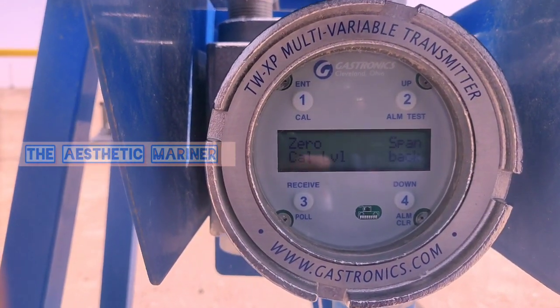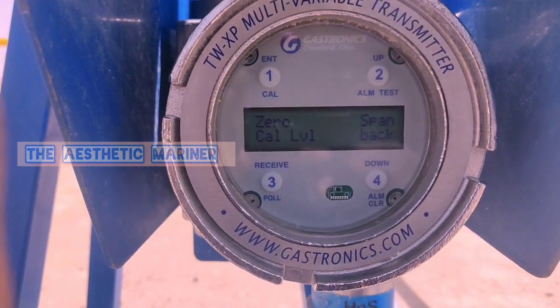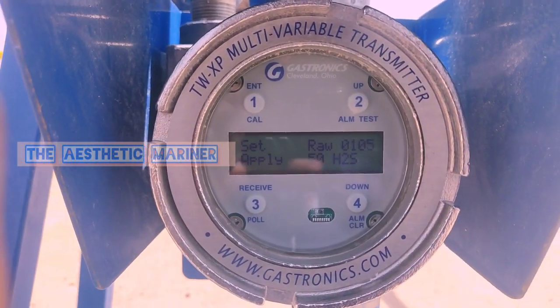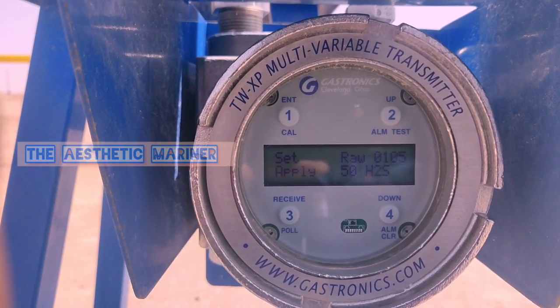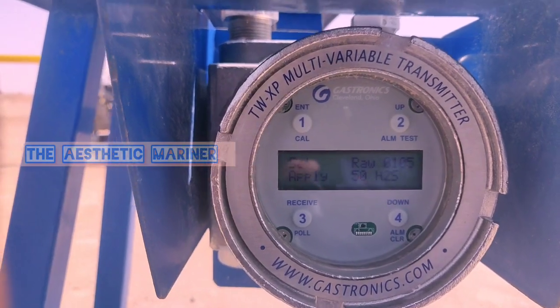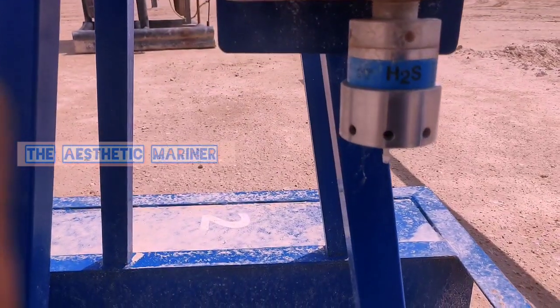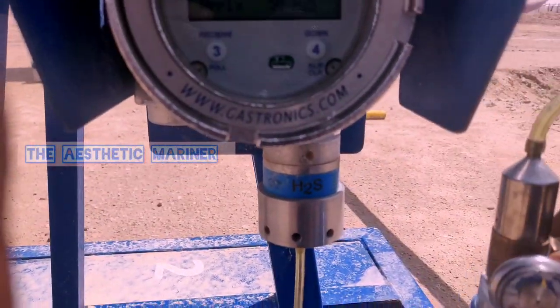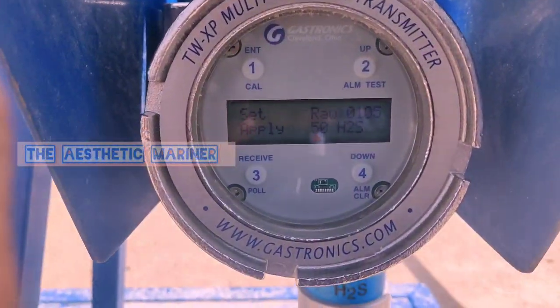Now the zero is saved and it is back to the calibration menu. We need to press number two for the span. It is showing set raw one zero five, so we will now apply the 50 ppm H2S gas to the sensor. The gas is turned on and the raw reading is now going to vary — it is going high.